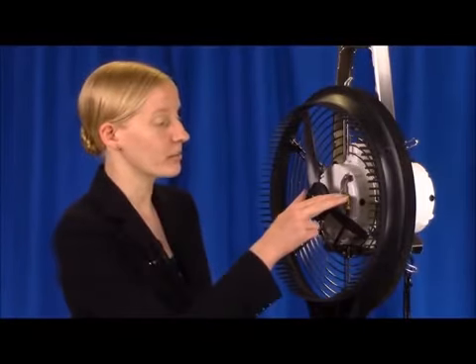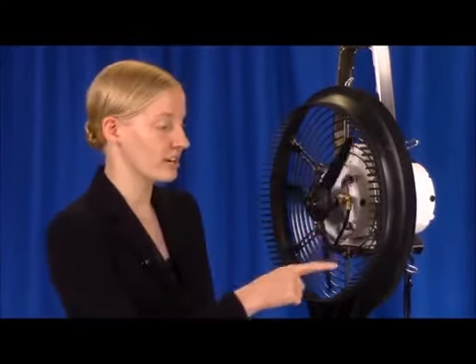Water is fed under ordinary pressure to the rear of the blade assembly where it enters a reservoir. The blade's rotation divides the water into internal passageways that extend the length of each blade. The water exits near the end of each blade where it meets a pinned venturi at high speed to complete the atomization.